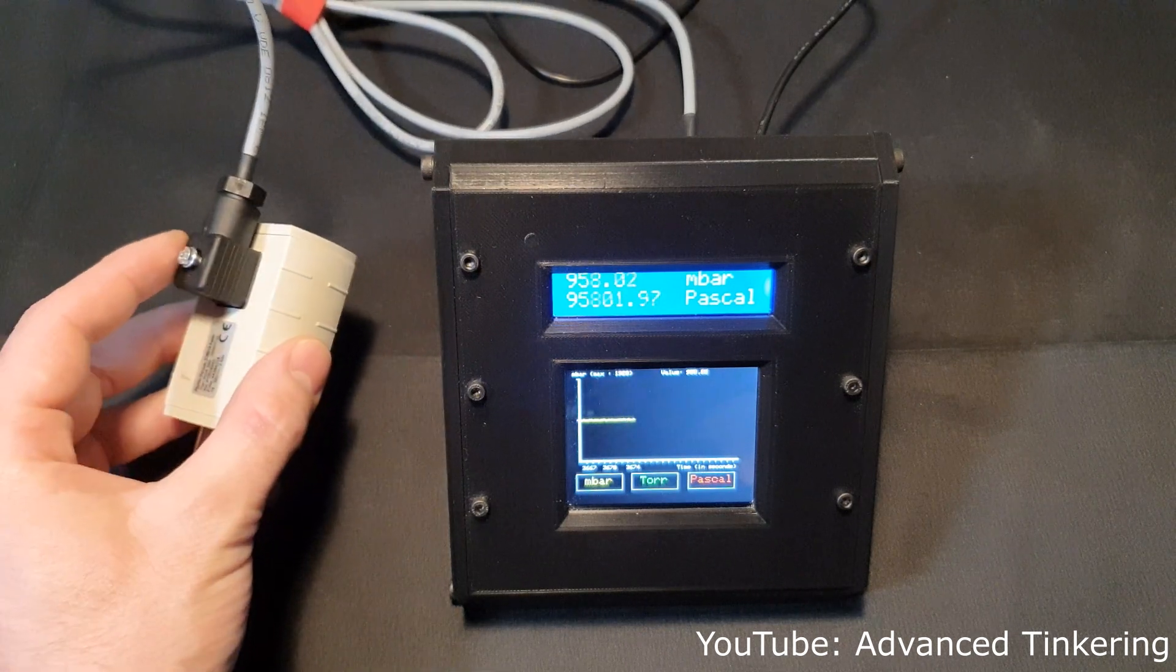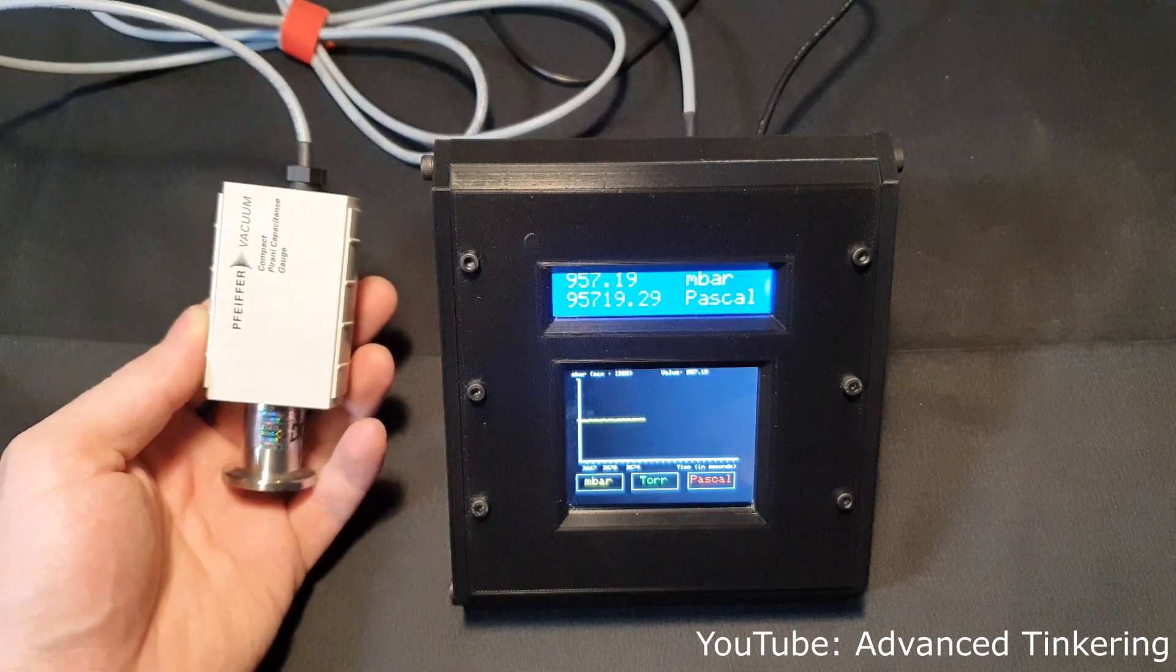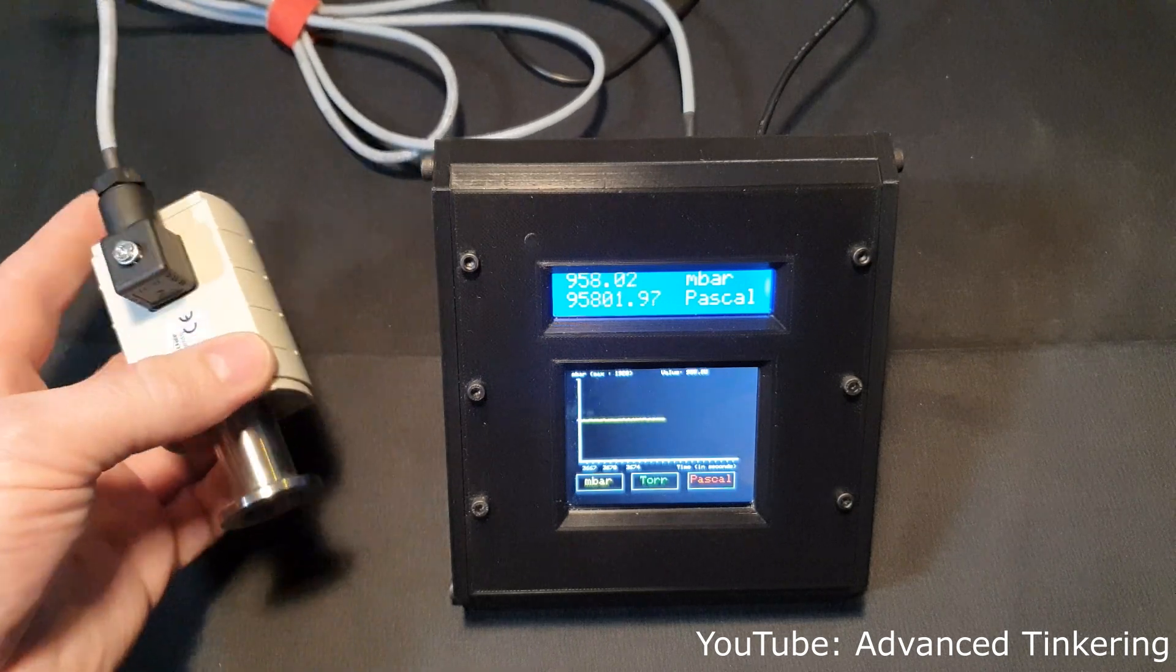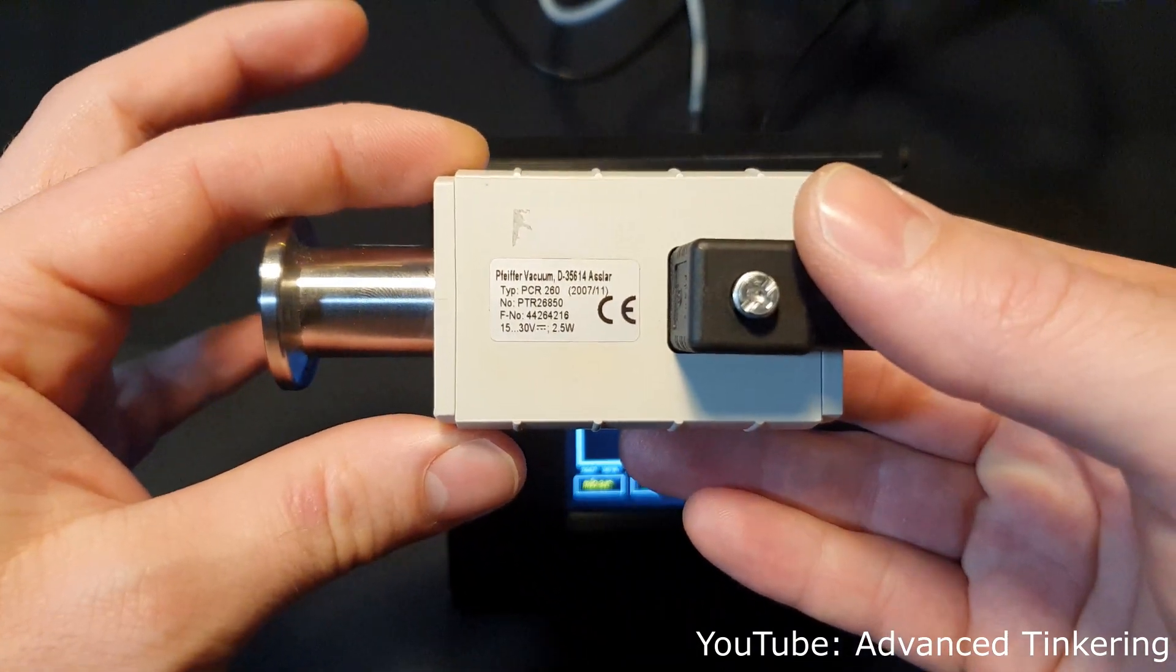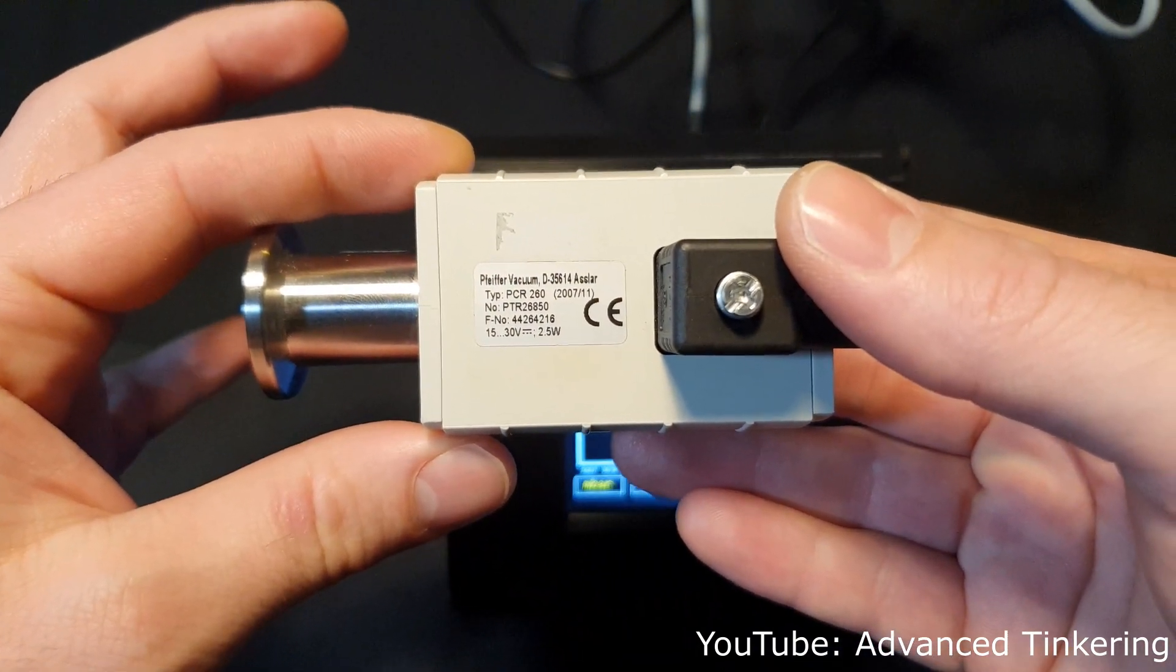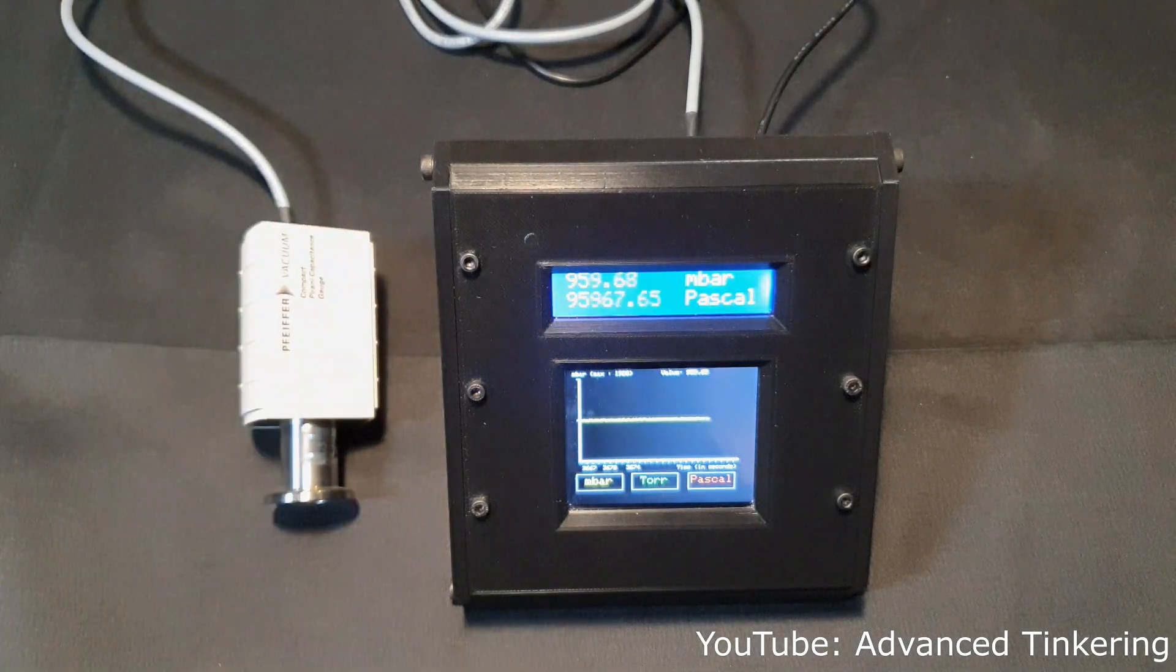The gauge you can see on the left side here is a Pfeiffer PCR 260. PCR means that it is a Pirani capacitance gauge, so it combines two measuring methods. On the one hand it uses the Pirani method, and on the other hand it uses the capacitance method. The advantage of this combination is that you can measure pressure in a broader range.